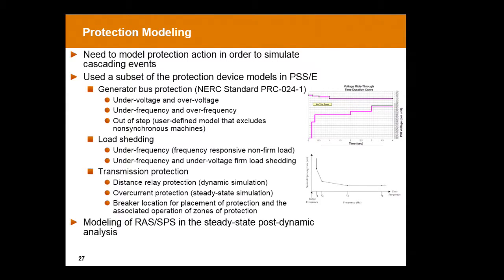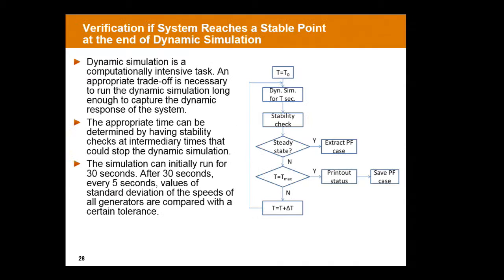For load modeling, especially load shedding, we need to model the under-frequency and under-voltage load shedding relays in order to trip load devices to protect them once voltage or frequency behave abnormally. For transmission protection, we need to add distance relay protection and overcurrent relay protection to make sure the simulation is accurate.